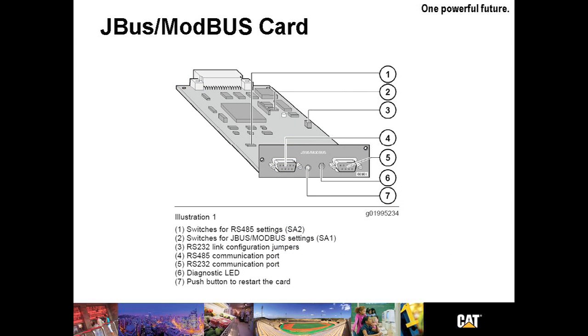The JBUS Modbus card provides UPS states and measurements in JBUS or Modbus protocols. The JBUS hexadecimal or Modbus RTU protocols are used in slave mode. The system provides a communication channel with an RS-485 or RS-232 interface.